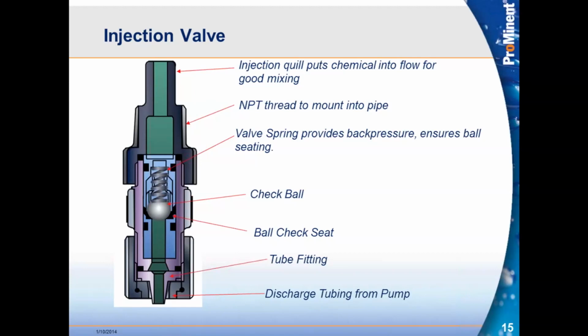So you see again our connector set, our tubing, our compression fitting is at the bottom here. That's the inlet. Then we're going to thread that. You see the NPT thread at the top. That's going to go into our injection point. Okay. Then we don't want the chemical necessarily to just go into the pipe and go along the sidewall of that pipe. That's where we have the slowest flow in that pipe. That's where we have the most friction. The flow is going to be slowed down in the set along the sides. So we want to get that chemical out into the center a little bit.